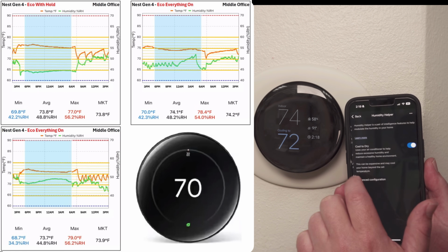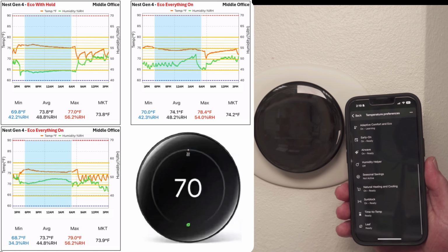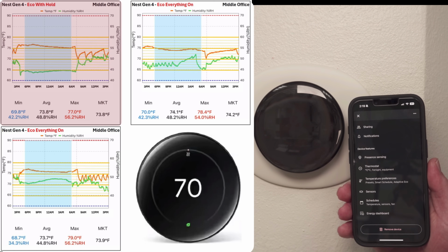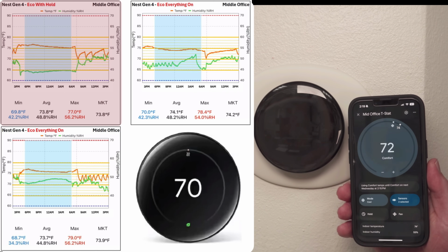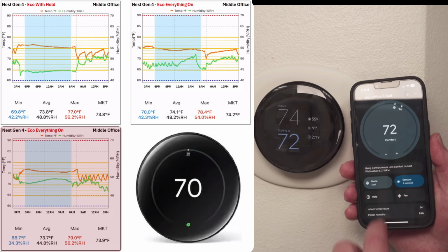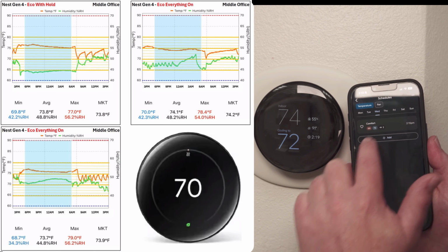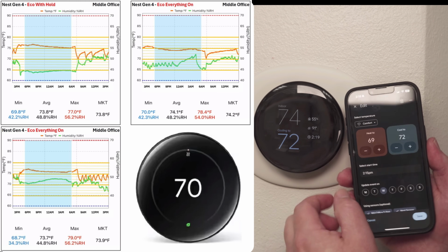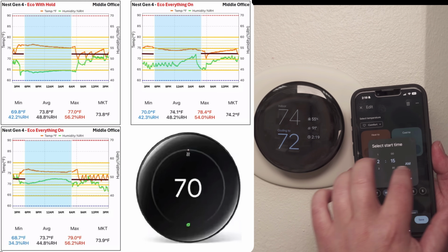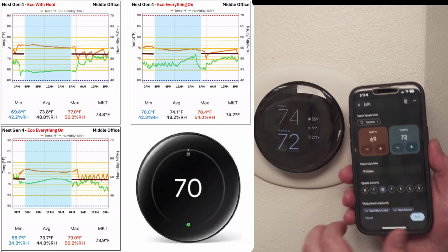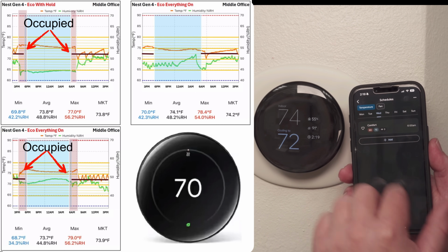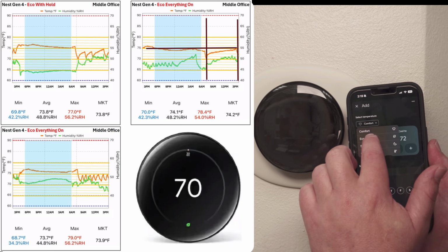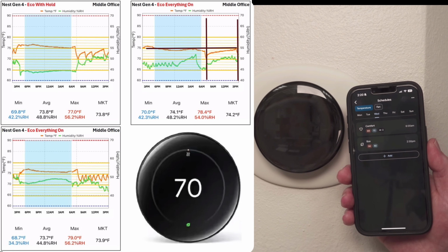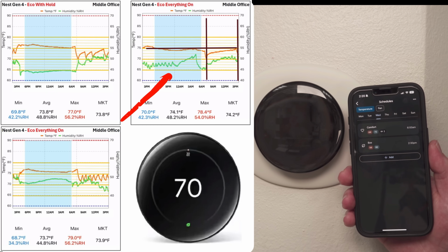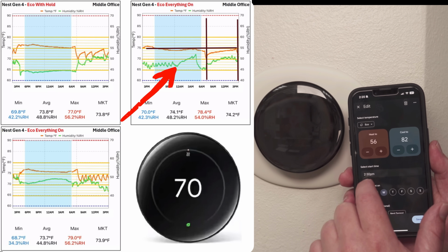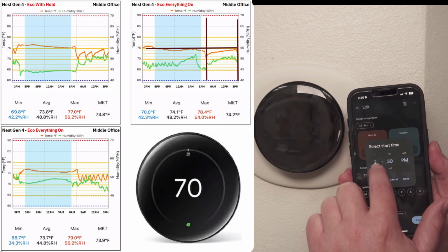Now let's look at the results for our Nest thermostat, with the exact same setup as the Ecobee. The first chart is from earlier where I added the hold. The second was recorded over a Sunday, and the last was that next Monday. The results are a little like the Ecobee - I had the schedule set for 72 degrees for comfort, which it pretty much never ran at. You can see it raises the temperature up to 76, 77 degrees even when the office was occupied. On the weekend it only cycled 2 times, because it's clear somebody left the door open - the green line showing humidity goes up and down, showing other units cycling and air from the common area making its way into that room.